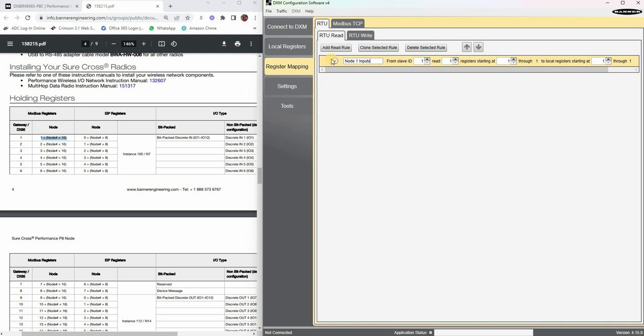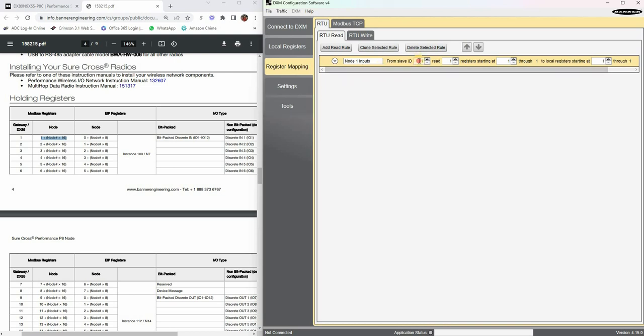From slave ID 1, which means if it's a radio and if it's on the performance network it is going to be slave ID 1 always. If it were a Modbus device, then the Modbus ID would be the slave ID in that case. If you were writing to the LEDs on the DXM you would be using a different slave ID just to give you a heads up.